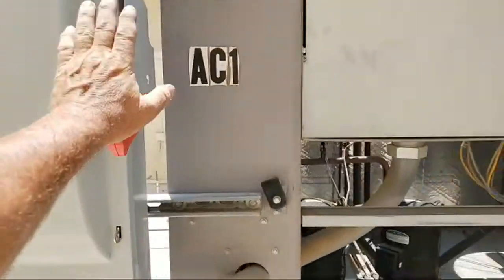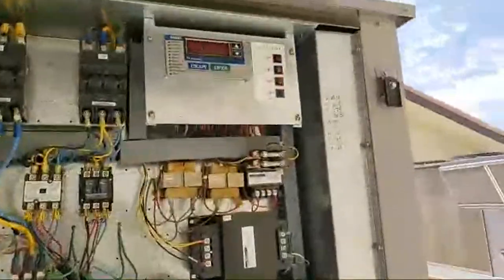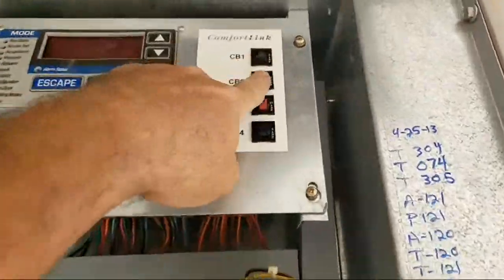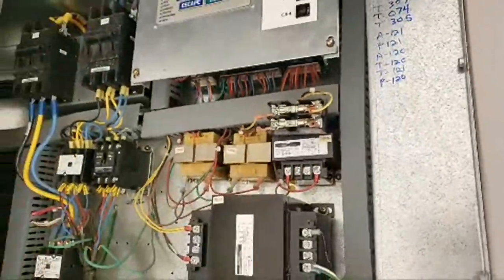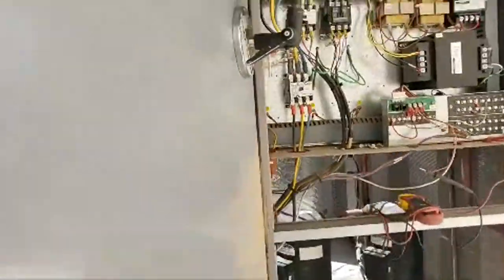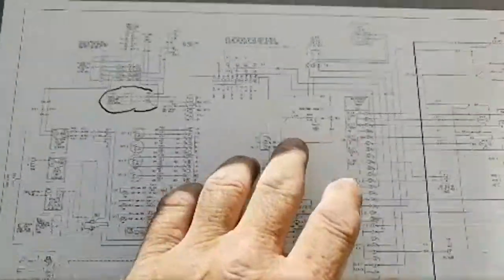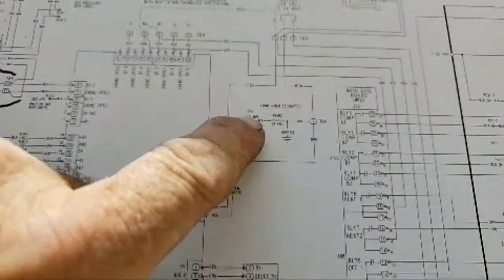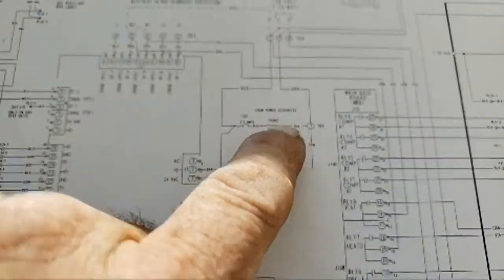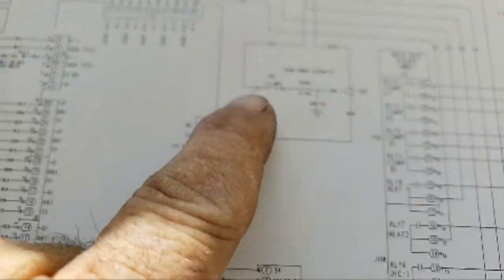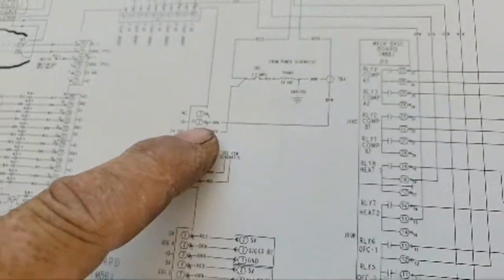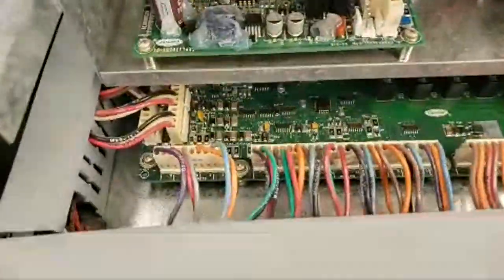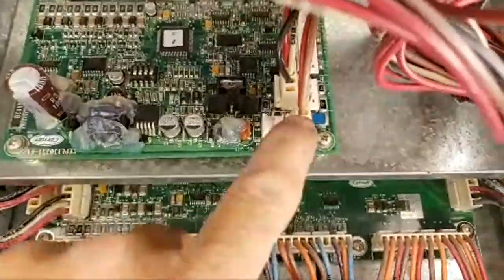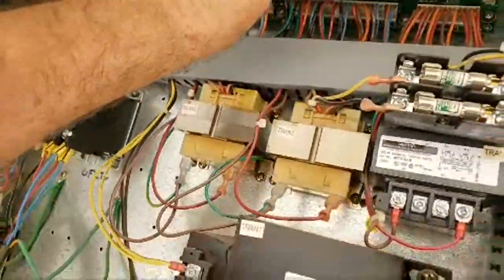But then I noticed in going through the controls that the big main unit here isn't running. Come up here. Controller's dead. This circuit breaker's popped out. Like, oh no, man. There's wires and sensors everywhere. Here's the schematic from CB2 coming off of the transformer right here. It goes to J1 of the main base control board. So I just unplugged that, which is this. Isolated it, still tripped.